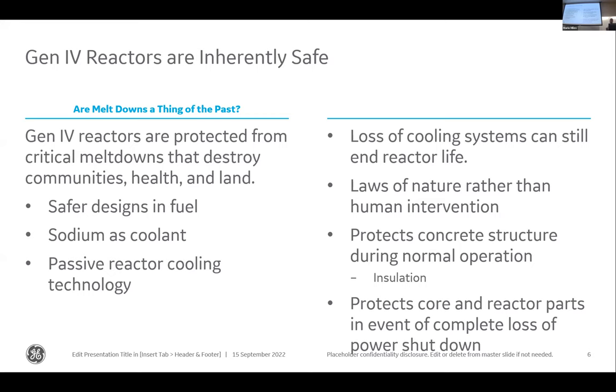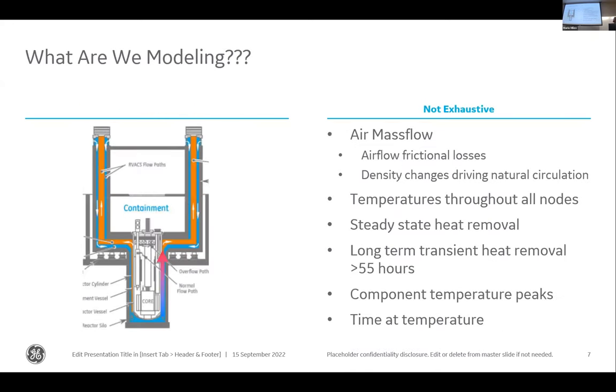One thing this system does is help protect the concrete structure during normal operation, though that's mainly covered through insulation. The real purpose of this modeling is to prevent excessive damage to the core in the event of a shutdown. We're modeling air mass flow through all airflow nodes, frictional losses, density changes driving natural circulation, temperature movement throughout about 1,000 nodes — now reduced — steady state heat removal, and long-term transient heat removal of 55 hours or more. We're mainly concerned with component temperature peaks and time at certain temperatures to deal with creep fatigue.